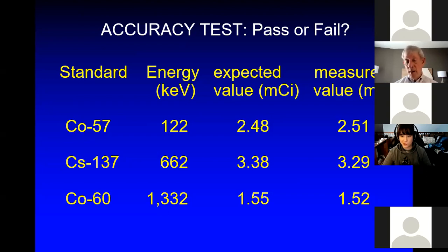The next one is 9 parts out of 330. That's a very small number. The next one is 3 parts out of about 150 something, very small number. All those are within just 1 or 2%. That's a beautiful accuracy test. Again, keep in mind that we are decay correcting those 3 isotopes and putting that number in the third column.